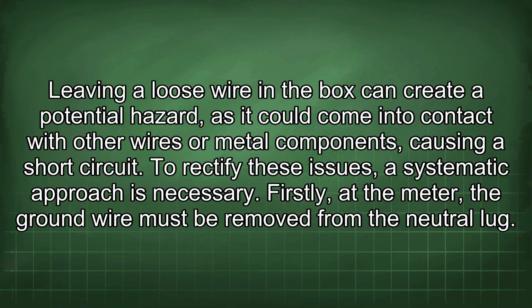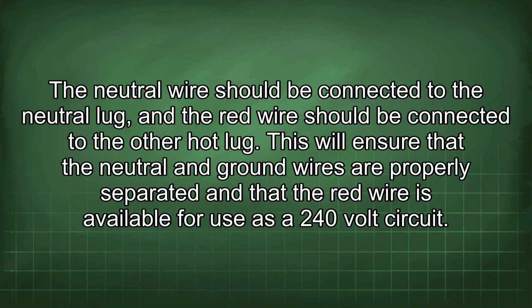To rectify these issues, a systematic approach is necessary. Firstly, at the meter, the ground wire must be removed from the neutral lug. The neutral wire should be connected to the neutral lug, and the red wire should be connected to the other hot lug. This will ensure that the neutral and ground wires are properly separated and that the red wire is available for use as a 240 volt circuit.